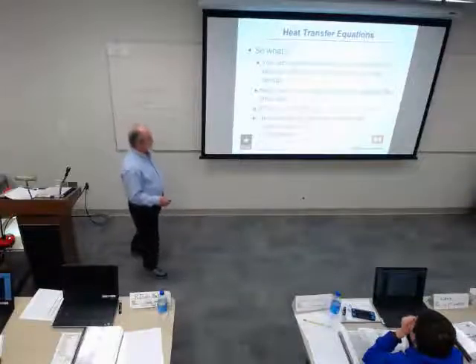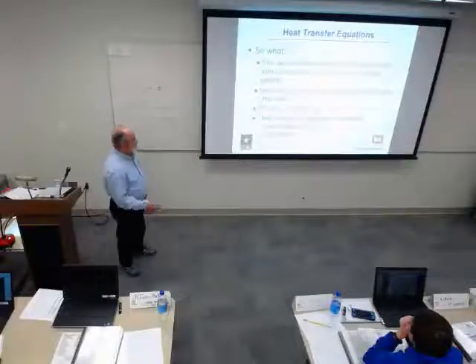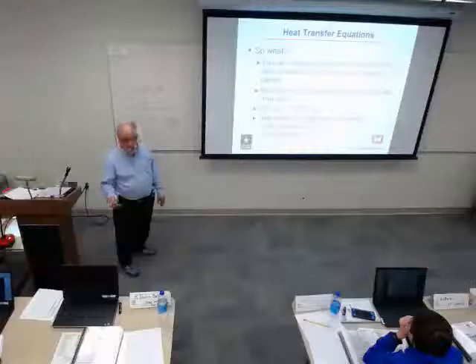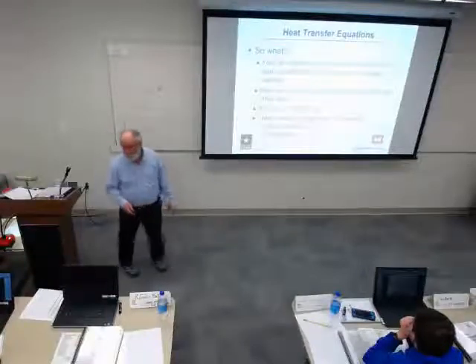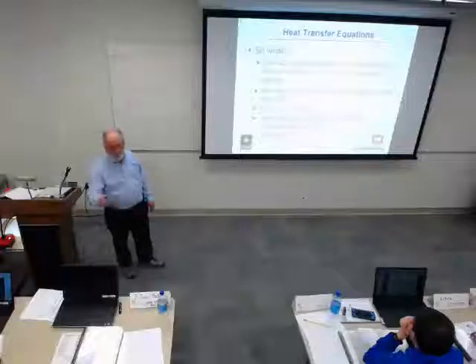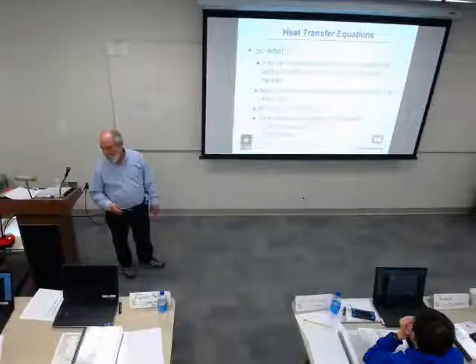So the BTUs per hour of the air should equal the BTUs per hour of the water, and it should balance. Otherwise, we know we've got trouble. We know that either the information that the guy wrote down on the report is wrong, or there's something wrong with the coil. And that's all we can say from that point: something ain't right. So go back out and check again, and while you're out there, see if you can find anything wrong. That'd be good to go out there with them.